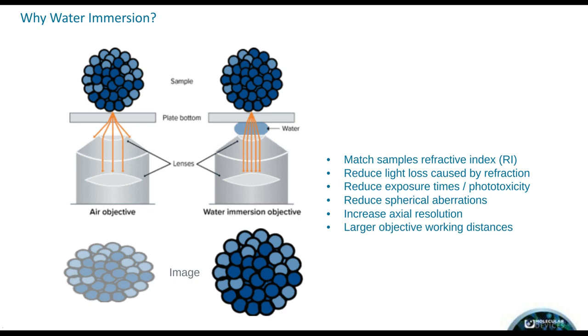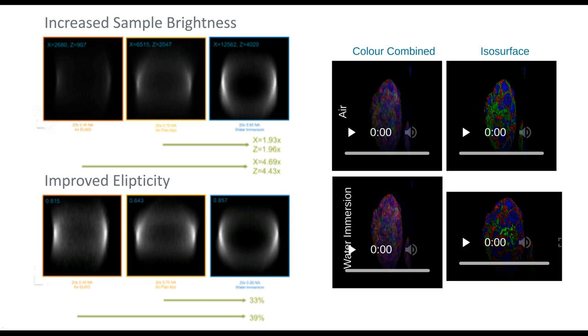Another important aspect is the ability to use different types of objectives — dry objectives from 1x to 100x, but also immersion objectives including water immersion objectives. This has an impact not only on reducing phototoxicity and exposure times and increasing resolution due to higher numerical aperture, but also because by maintaining the same refractive index between the water-based sample and the immersion medium of the objective, you have improved ellipticity of your sample compared to dry or air objectives, which would lead to much more disruption in terms of image quality.